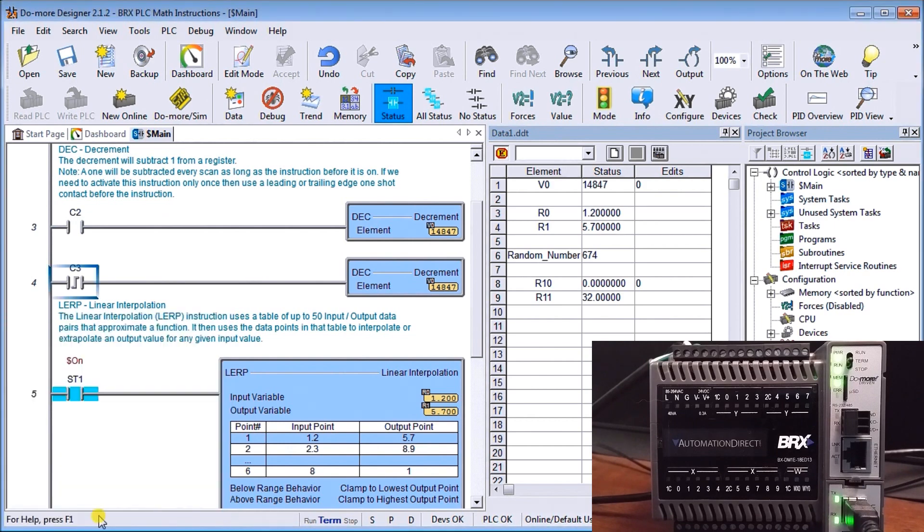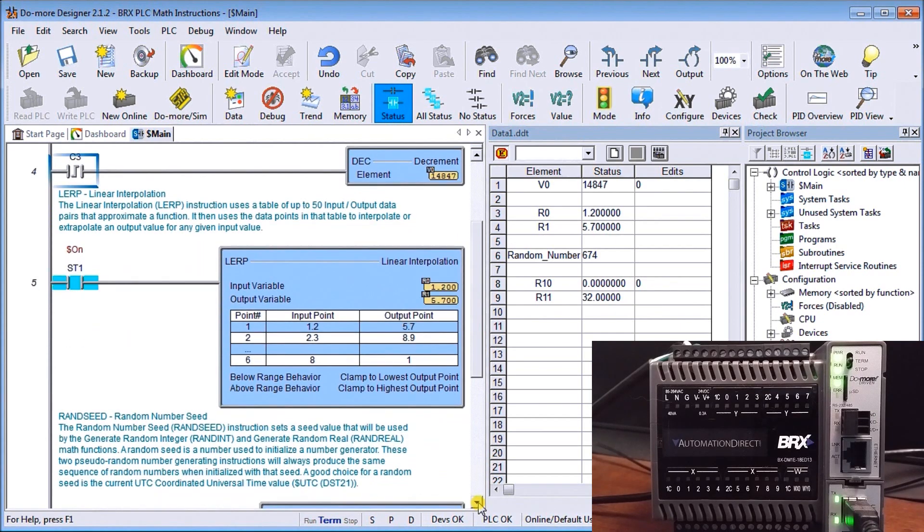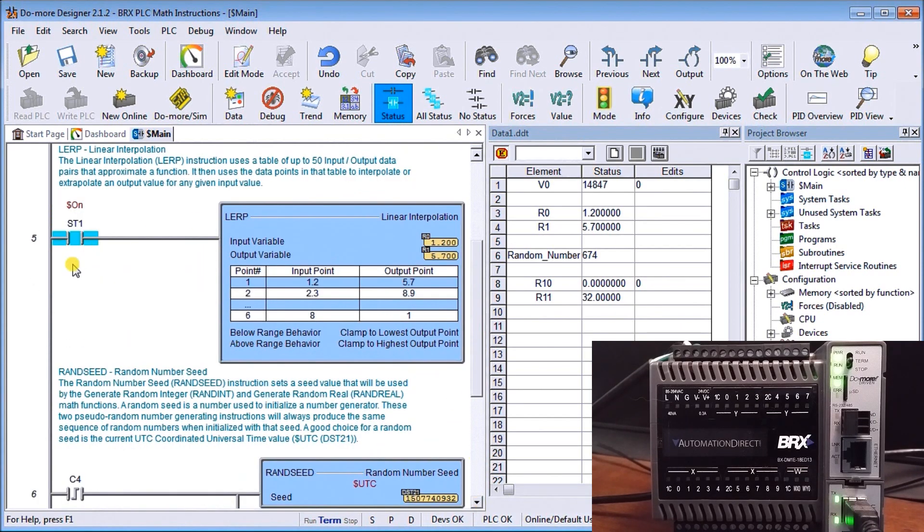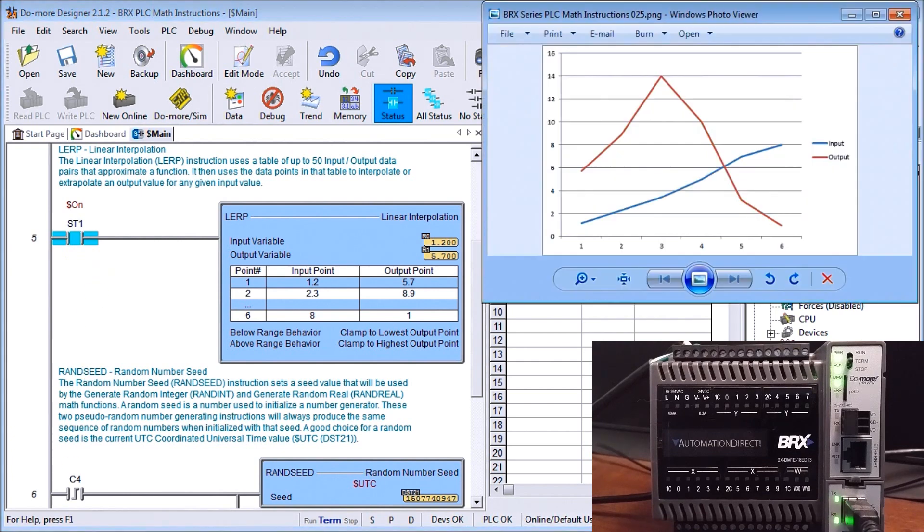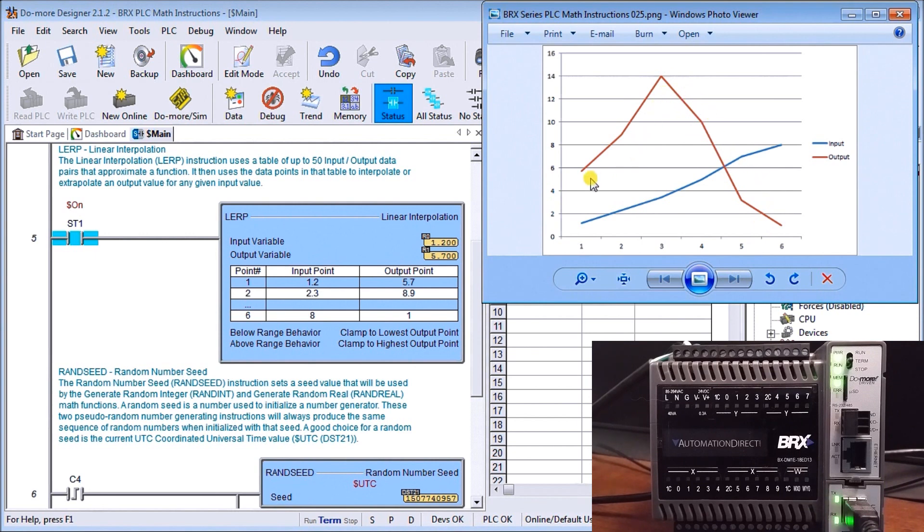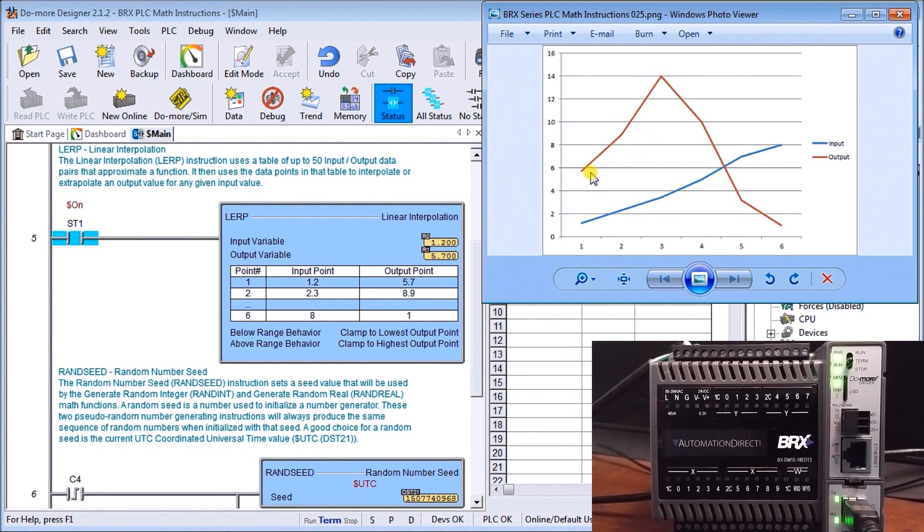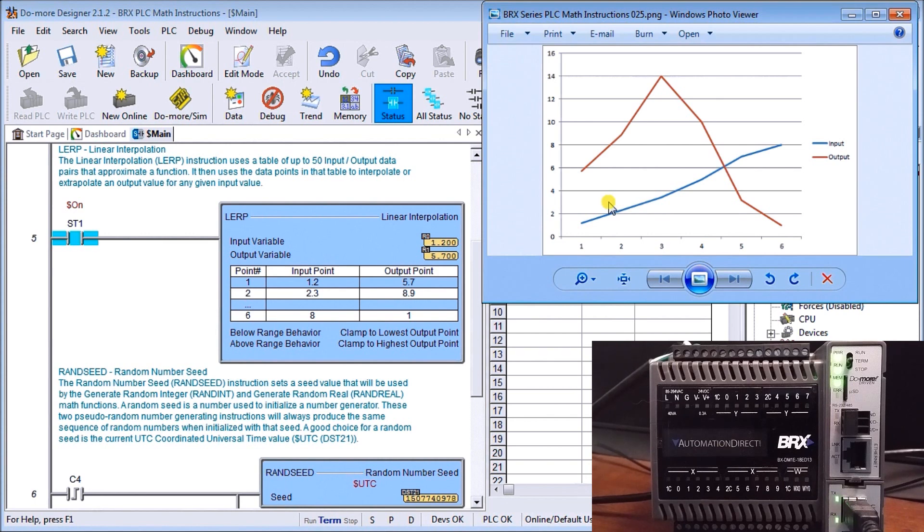The next instruction is linear interpolation. What that basically will do is we plot out a series of inputs and output points that interpret whatever I put as the input, and the output will be corresponding on our output variable. It's easier to see this if I look at a chart. Here's my chart. The blue line is my input, the red line is the output that I want, and I've plotted six different points on this curve. As I put an input point in, I get the corresponding output point on my red, and you can see it's linear between these two sets of points. I can have up to 50 input and output points working in pairs, and it extrapolates the output value for any given input value.